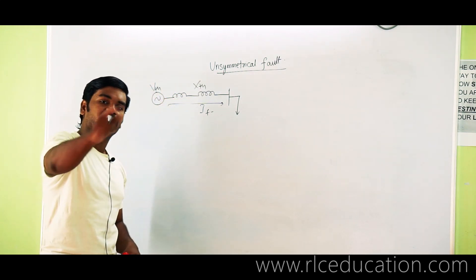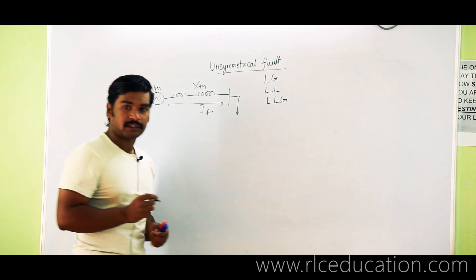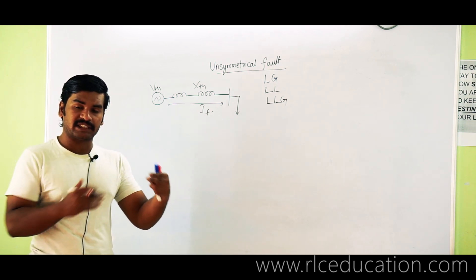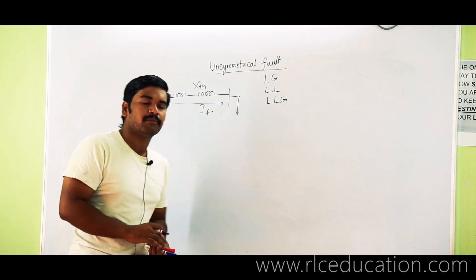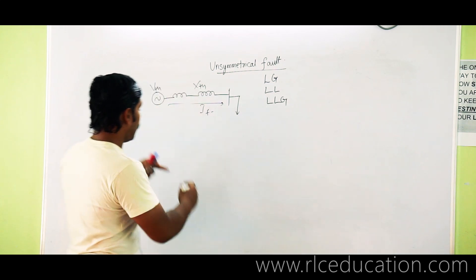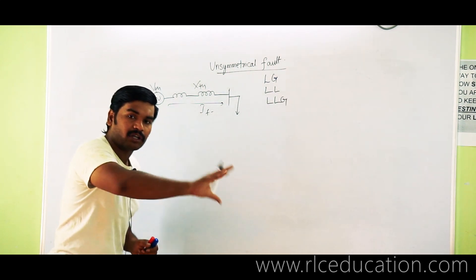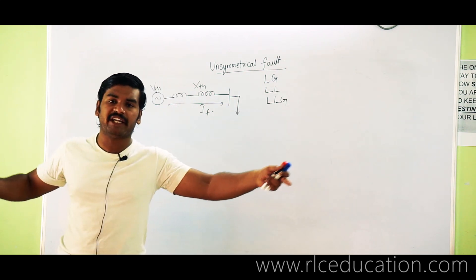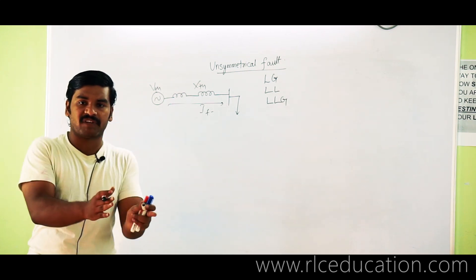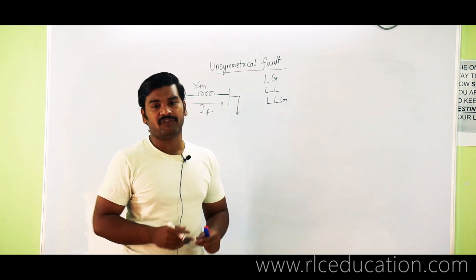In unsymmetrical faults, this condition of symmetry is disturbed. The types of unsymmetrical faults are LG fault, LL fault, LLG fault. In these cases, fault current flows in only one or two phases; the other phase has no fault current. That means symmetry is disturbed and the single-line diagram is no longer valid. We would have to take three separate reactance diagrams — one for each phase — and calculate all fault currents, which becomes very tedious.